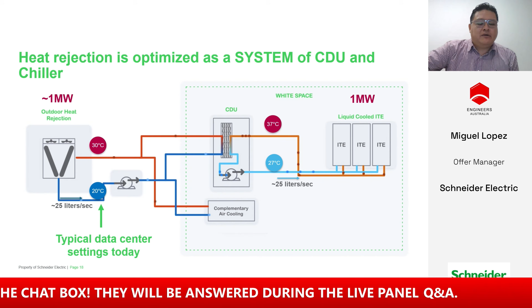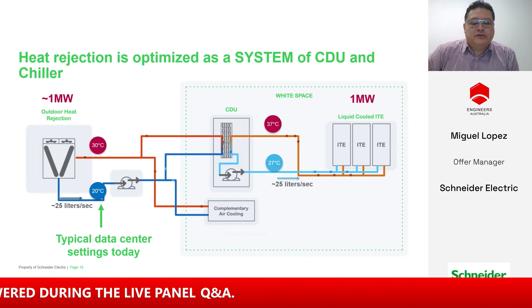Okay, moving along, as they say, a picture tells 1,000 words. So the following slides are just depicting some of the possible configurations. And in this case, we're talking about water temperatures. In the white space, we've got water temperatures back to the CDU of 37 degrees and out to the heat exchanger of 30 degrees. So just bear that one in mind. The temperature difference now on the hot side is 7 Kelvin or 7 degrees. And this is, for example, a 1 megawatt site. For reference, the water supply on the technical loop is 27. On the facility water, it's 20.